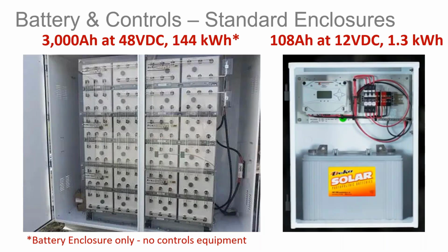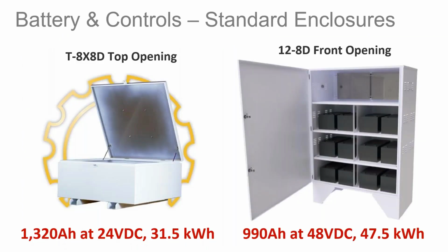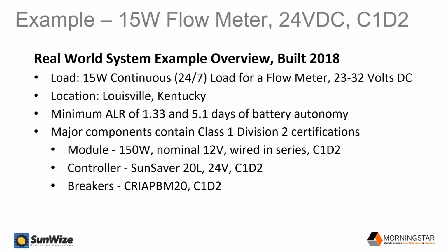Here's an example on the left. That's a dedicated energy storage housing. That's a Unity battery bank of about 3000 amp hours at 48 volts, or 144 kilowatt hours. And then on the right, you'll see a real common example for a single battery pole mounted enclosure with a ProStar PWM along with all the other control circuitry. A couple more examples of the different flavors and formats of enclosures that you might see. This is going to come into play in the presentation as we start to talk about the design architecture of these larger systems and loads as they grow in size.